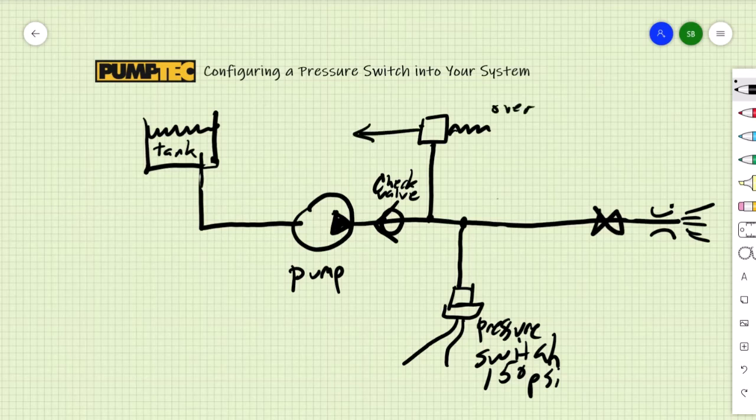I would recommend the overpressure device be set higher than the pressure switch, which in this case may be 170 psi.